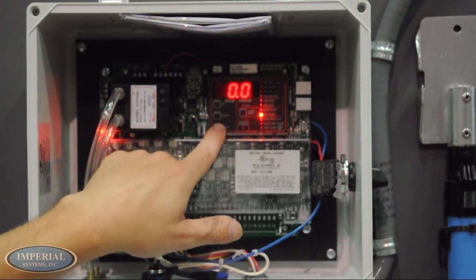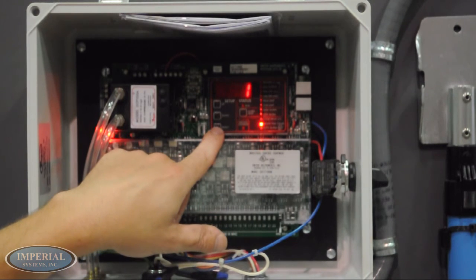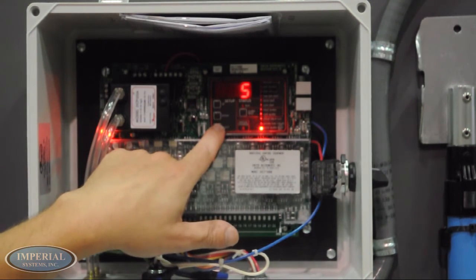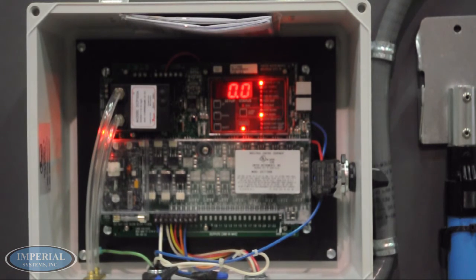The cycle delay by default should be at 0. Downtime cycle is set to 0. Auto alarm reset is set to 5 seconds. Return to the process setting, press alarm reset, and the C-Max will be in run mode. The selector switch on the side of the control panel should be set to On Demand.